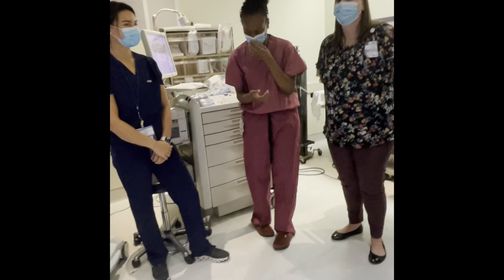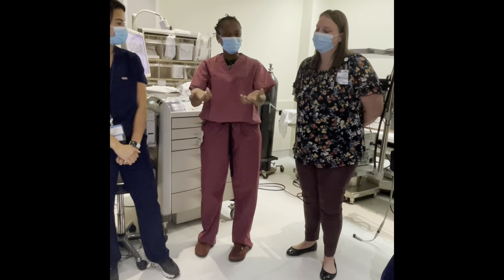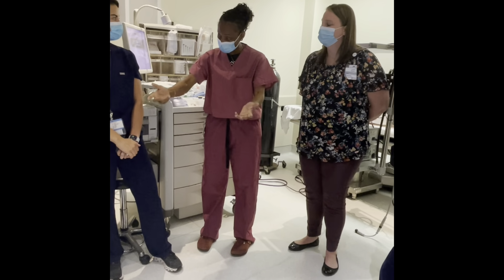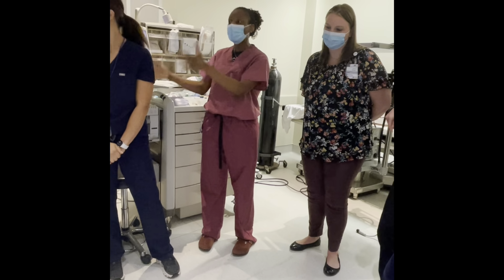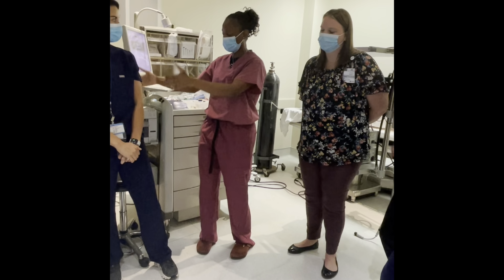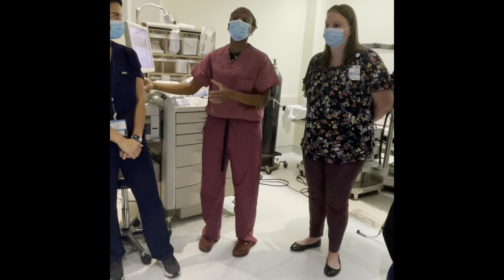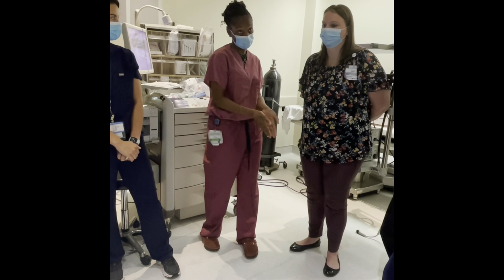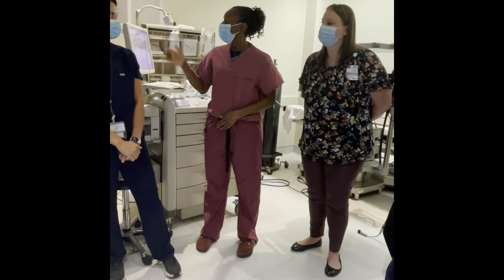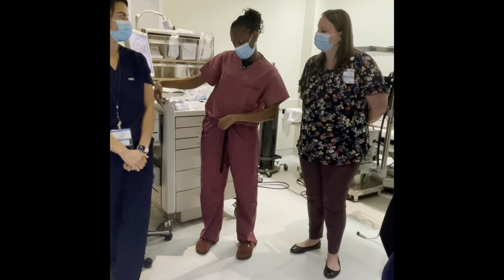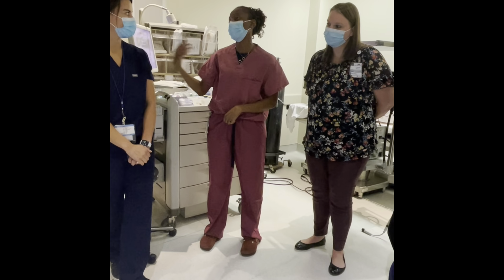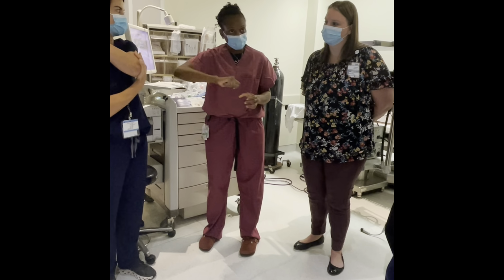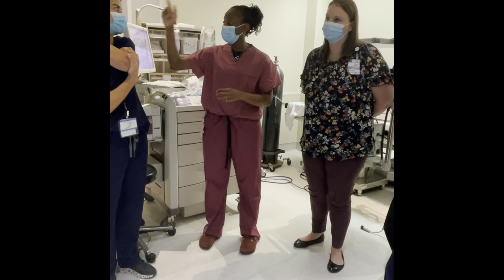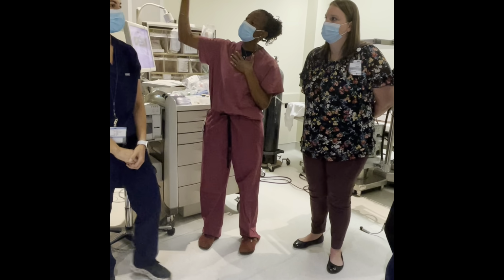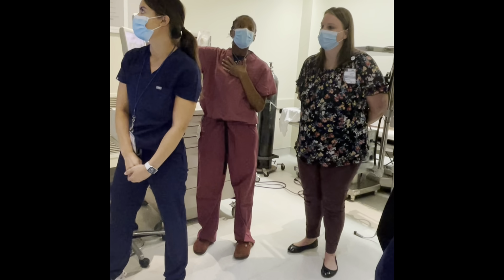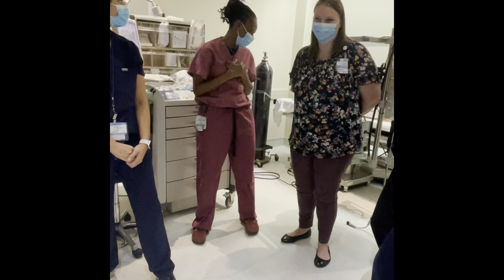Yeah, probably. Thank you. So in the back of the machine you have the wrench, right? You remember you have that wrench in the back that opens and closes the cylinder, right? So the cylinder itself is high pressure because it's based on the volume in the cylinder, until it gets to the regulator, right? And then the pressure gets downgraded at the regulator, right? So when you check the machine and the cylinder, you always want to make sure you turn it off again, right? Because the machine will preferentially get oxygen from the pipeline. Does anybody know why? Yes, I know. Okay.